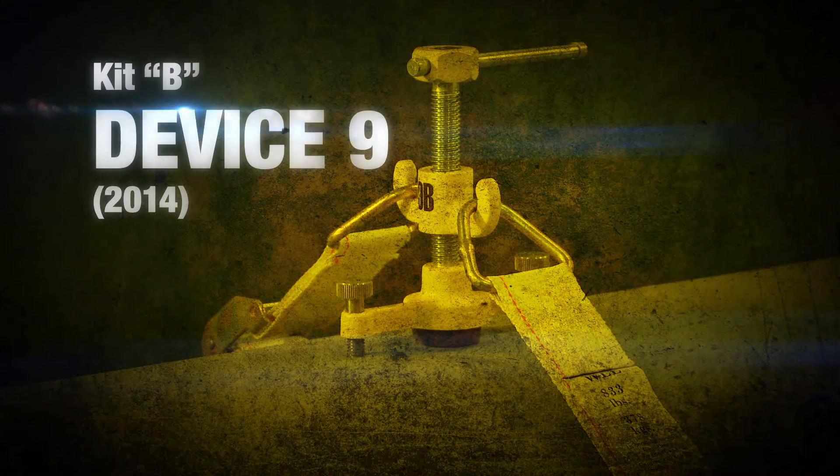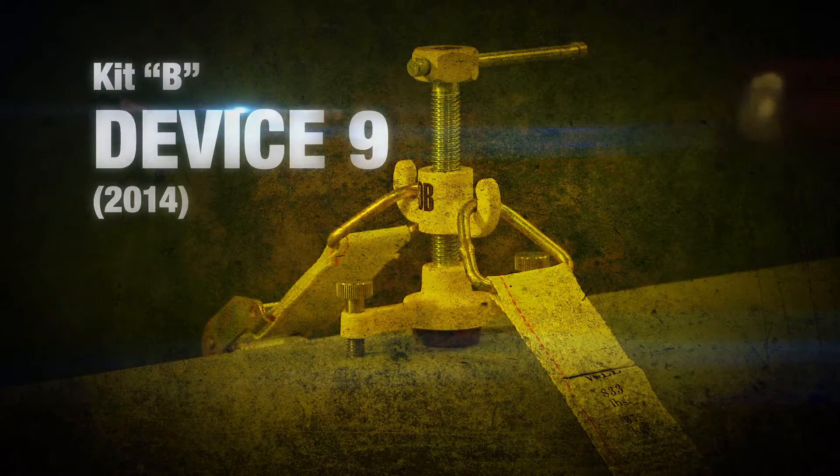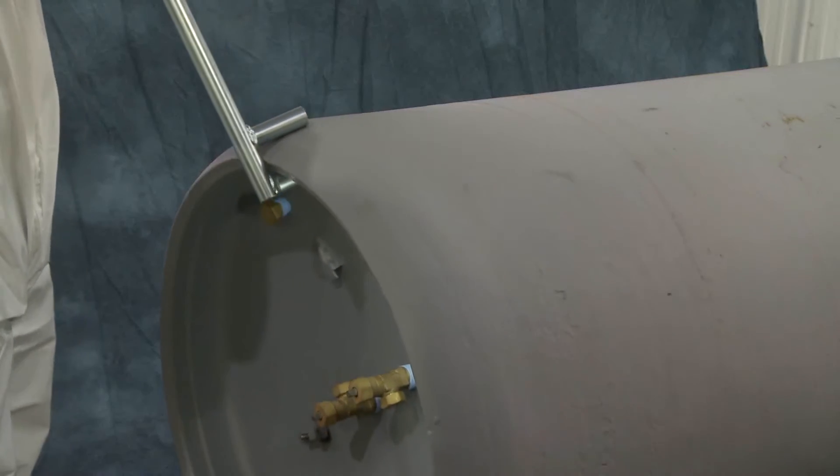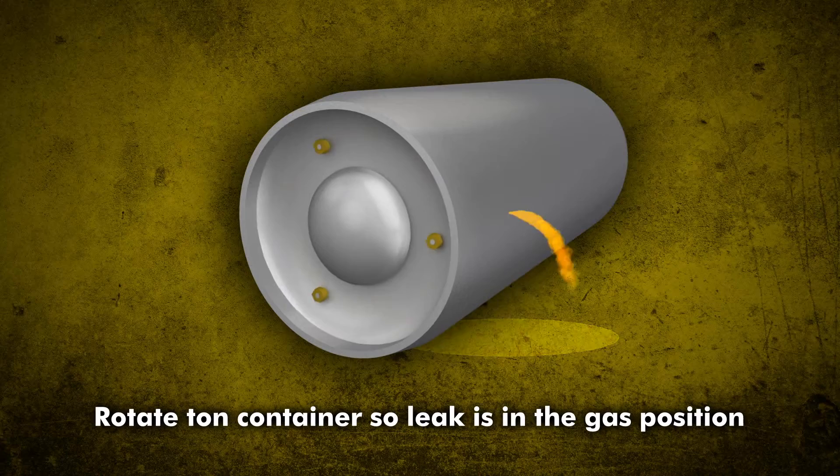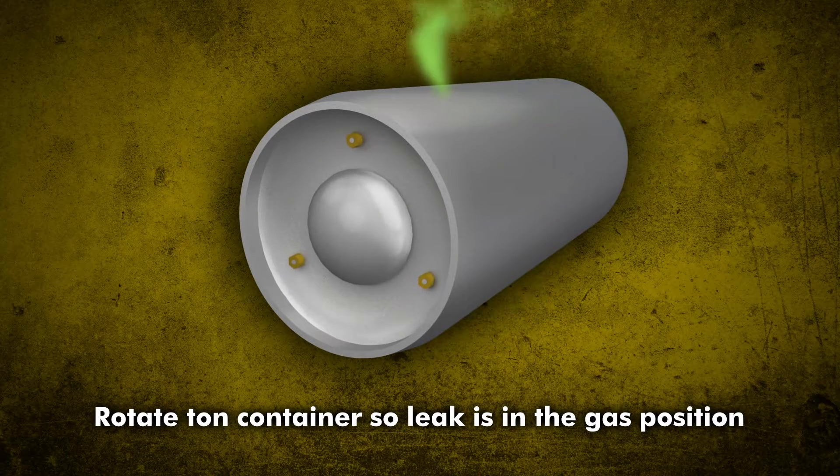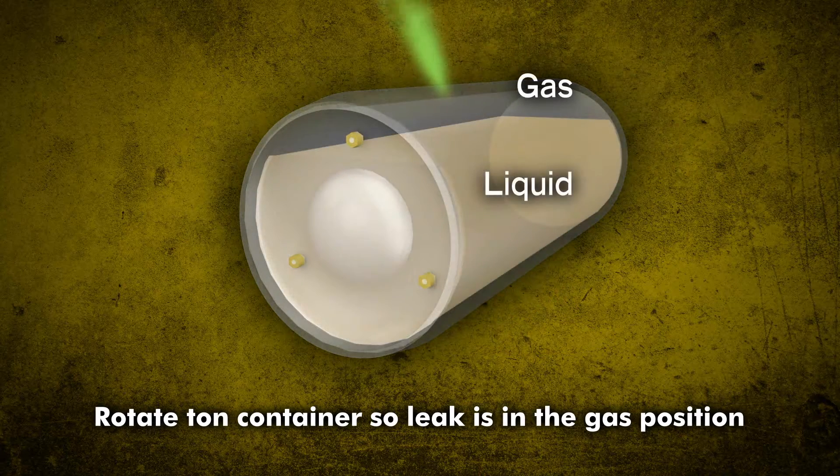A leak in the container sidewall can be contained by applying device 9. First, position the container on its side and rotate it until the leak is on the top. This results in a chlorine gas leak and not a liquid leak.